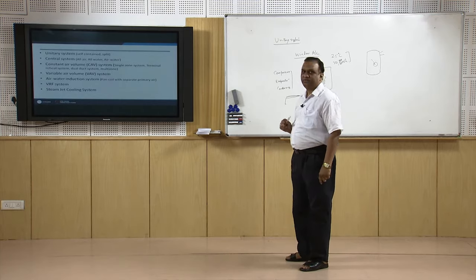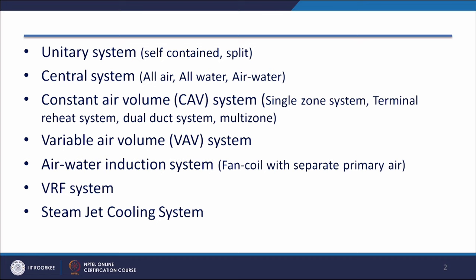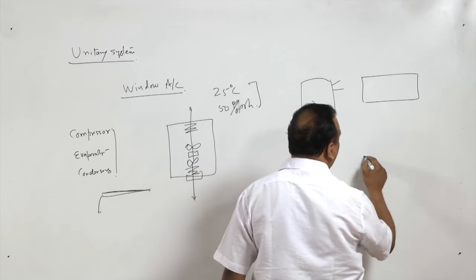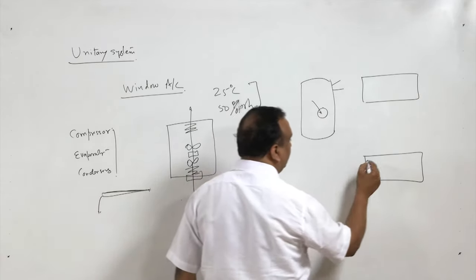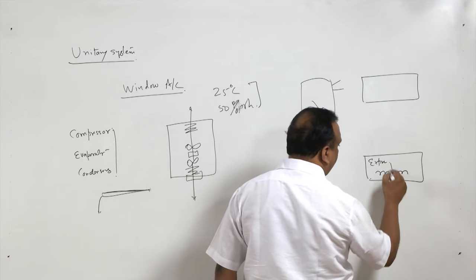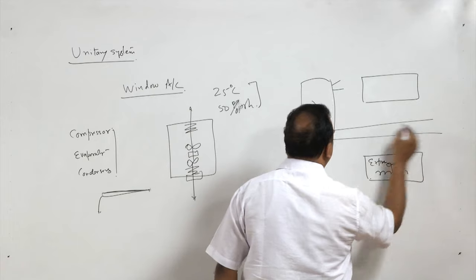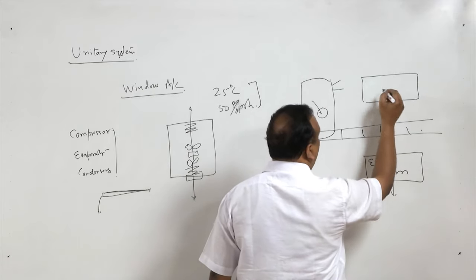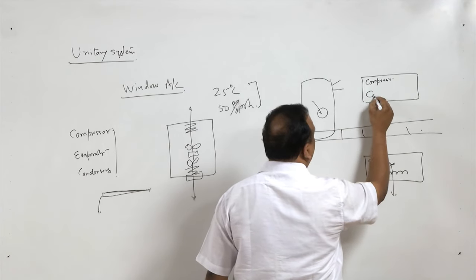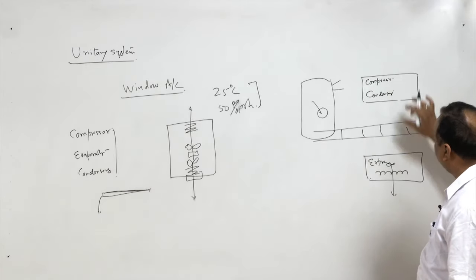Another type of unit in a unitary system is the split type system. In the split system, there is a split between the high pressure side and the low pressure side — there are two units. One unit has only the expansion device, evaporator coil, and a fan which blows air over the evaporator coil. This is the inside unit. Outside this, connected through the wall, is the outside unit which has the compressor and condenser, with a separate fan for each unit.